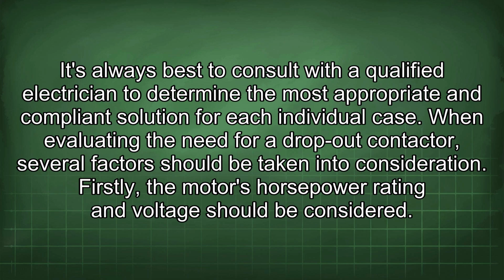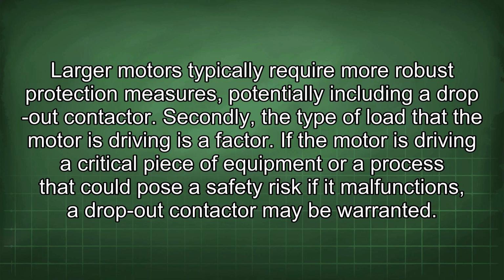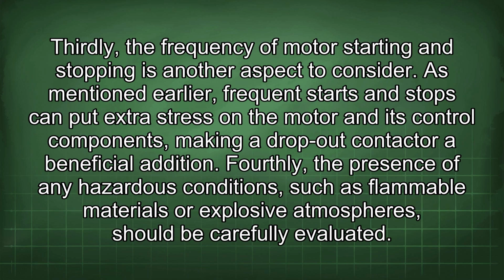When evaluating the need for a dropout contactor, several factors should be taken into consideration. Firstly, the motor's horsepower rating and voltage should be considered. Larger motors typically require more robust protection measures, potentially including a dropout contactor. Secondly, the type of load that the motor is driving is a factor. If the motor is driving a critical piece of equipment or a process that could pose a safety risk if it malfunctions, a dropout contactor may be warranted. Thirdly, the frequency of motor starting and stopping is another aspect to consider. As mentioned earlier, frequent starts and stops can put extra stress on the motor and its control components, making a dropout contactor a beneficial addition.